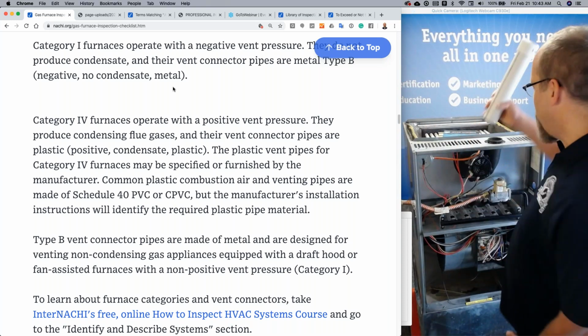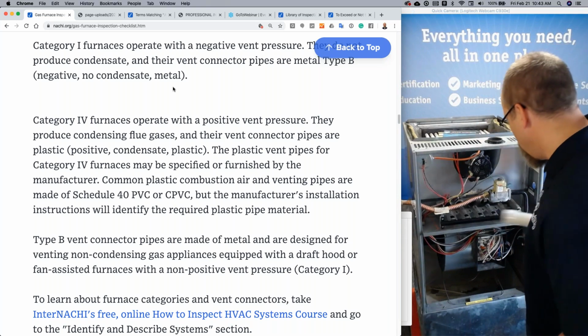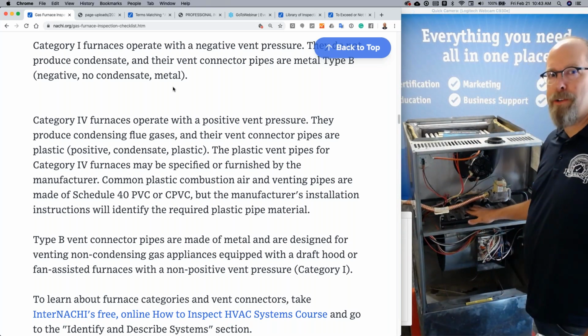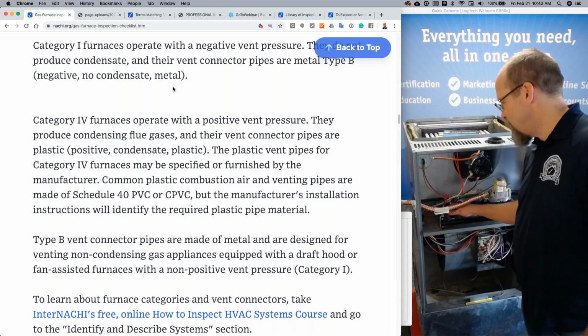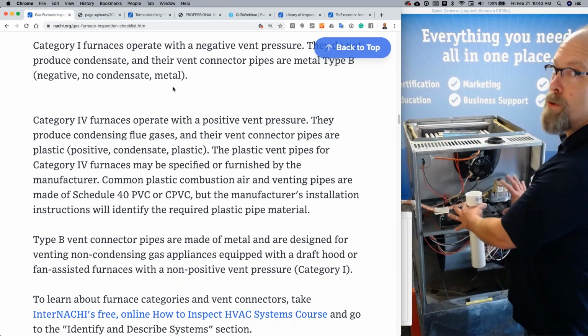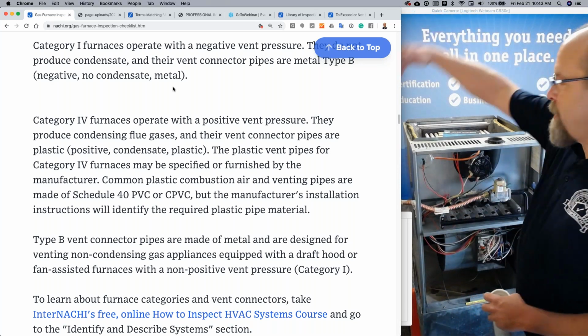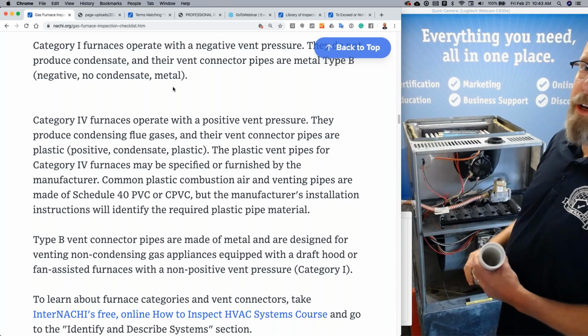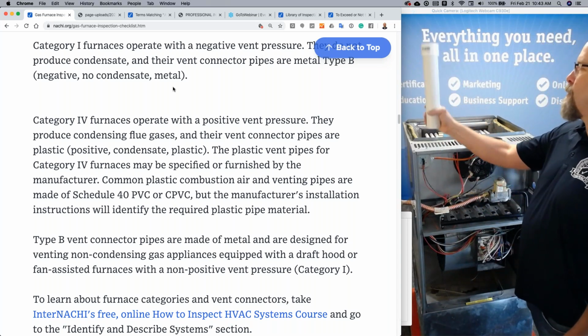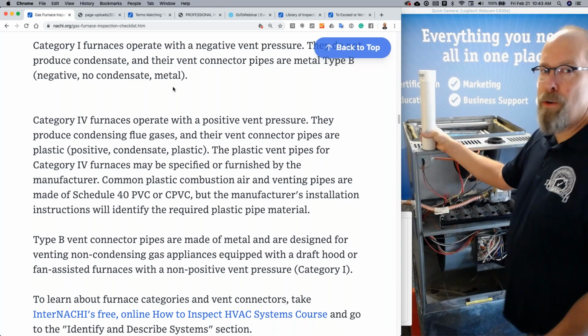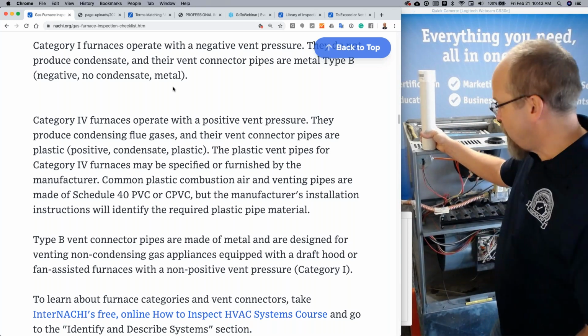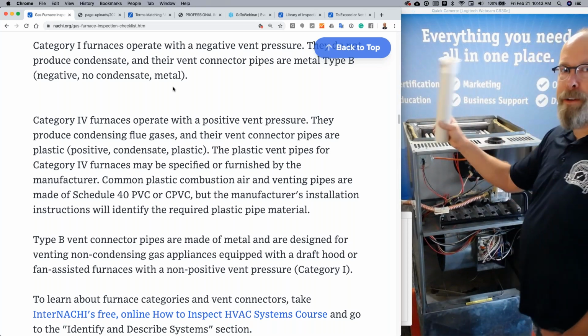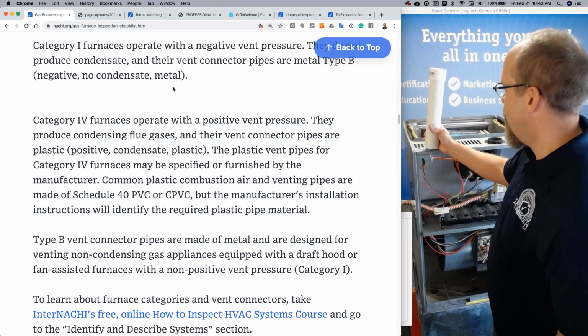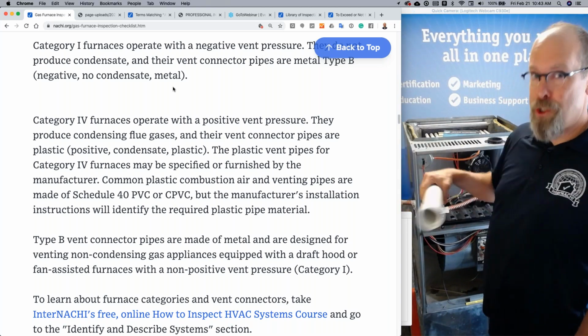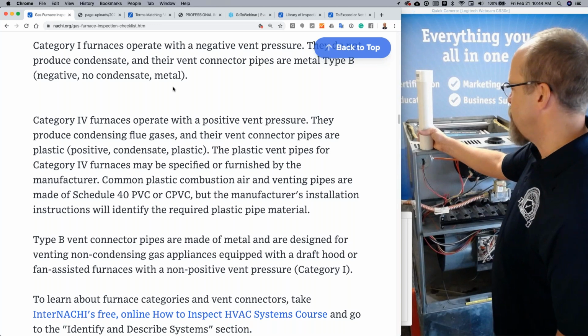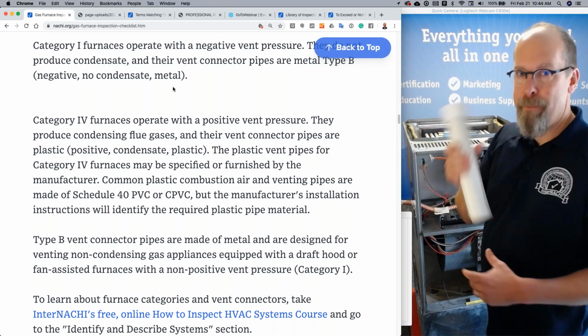And on a category 4 plastic vent pipe, condensate producing, you wouldn't see these burners. You wouldn't be able to touch the burners, the ignition source, any of the elements inside. It would be enclosed. And you'd have fresh air intake for the burners. That's category 4. Usually 2 pipes. Category 4, high efficiency, burns most of the fuel. We're talking 90% or more efficient, very little wasted through the exhaust gases. So it's a really good system to install. It's expensive in the front end, but it should pay for your investment over the long term, the life of the unit. So category 4, plastic pipes.